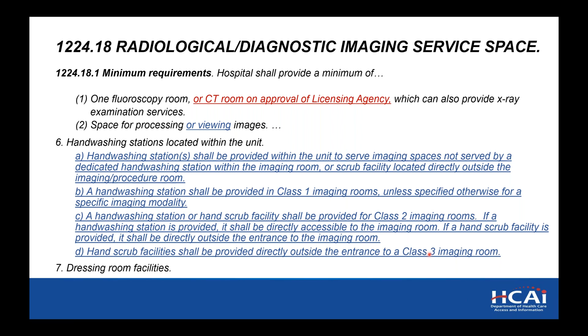For radiation protection, again, just breaking down the requirements for class 1, 2, and 3. It's basically the same thing we would require now. It's just adding the information about the control stations and the control alcoves. And then again, what we base our decision on is the physicist's report. So you're still going to need that.